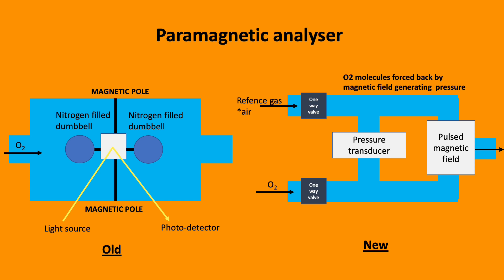Older paramagnetic oxygen analyzers contain two nitrogen-filled spheres. Nitrogen is used as it's not attracted to a magnetic field, and these rest over poles of a magnet. Oxygen is attracted towards the magnet, causing displacement of the dumbbells as they rotate, which is detected by a light source and photo detector.